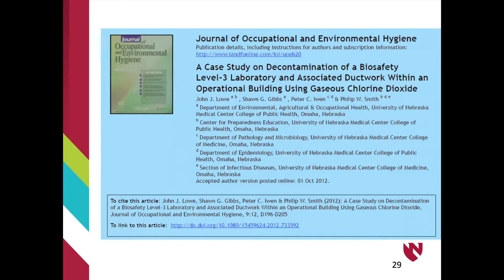This was one of the studies we did over those 3 years, looking at the gases, and this was looking at ductwork that spanned about 8 different floors of a university tower. We had a select agent rule-out lab, and its negative pressure air handling spanned 8 floors. It actually went through our medical library, that ductwork. And so we evaluated and validated how to decon with gas a span of contaminated ductwork.